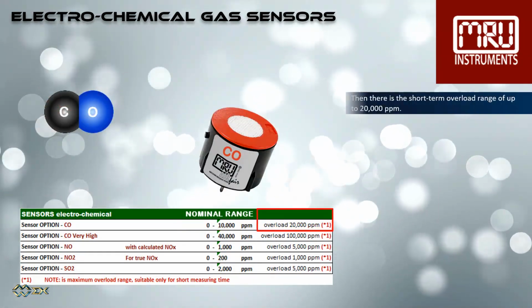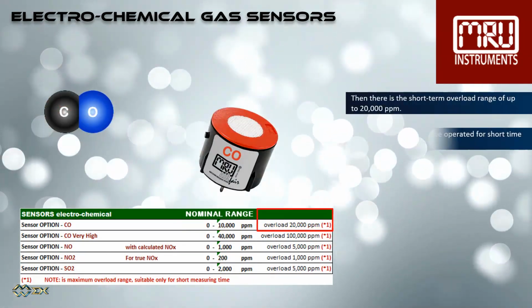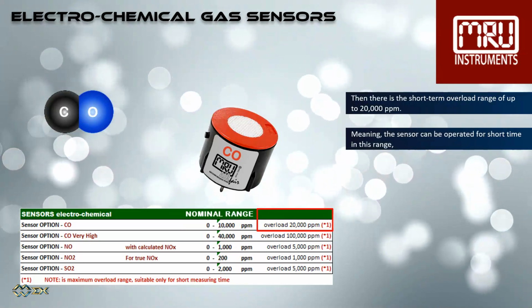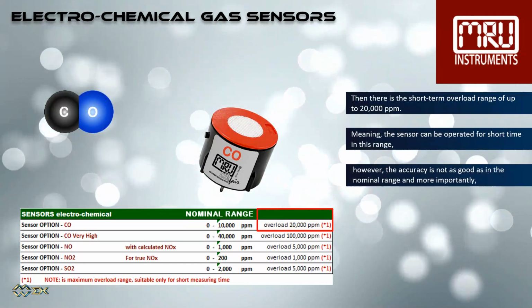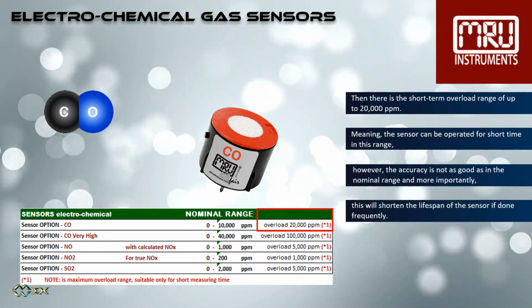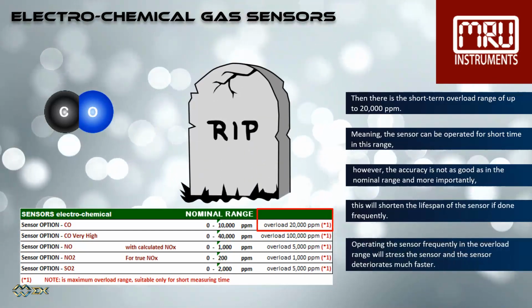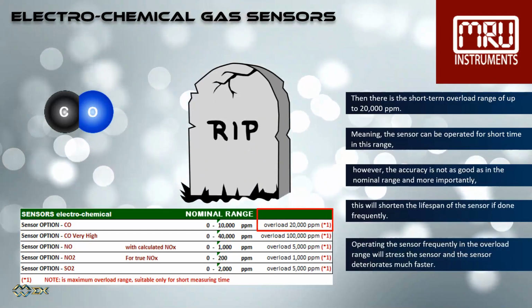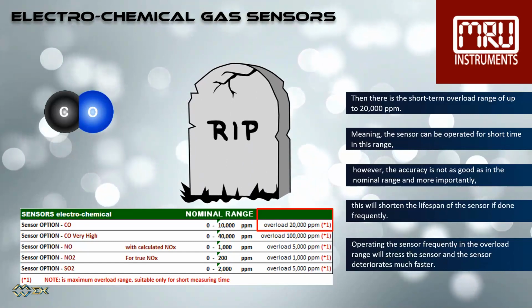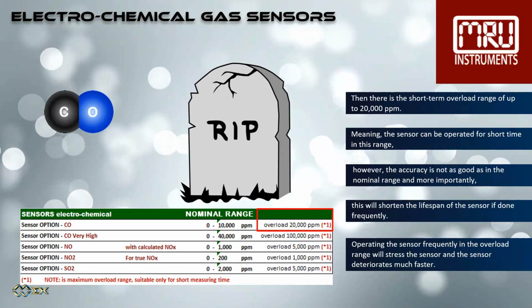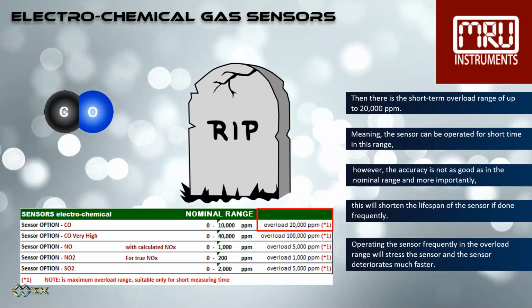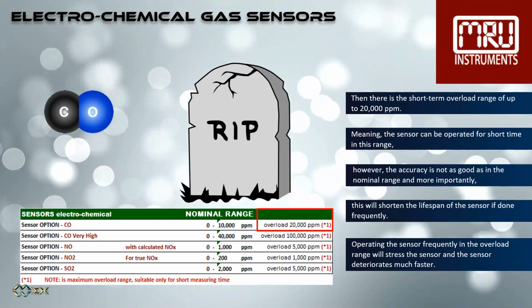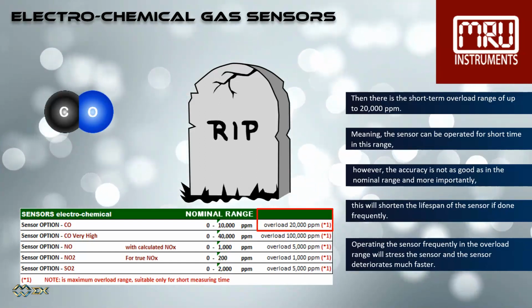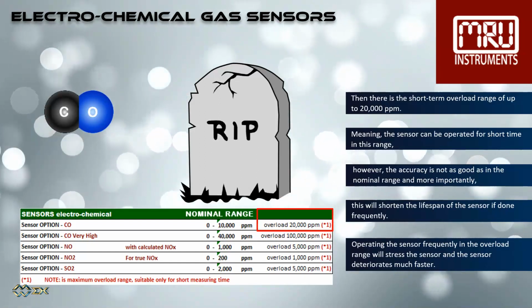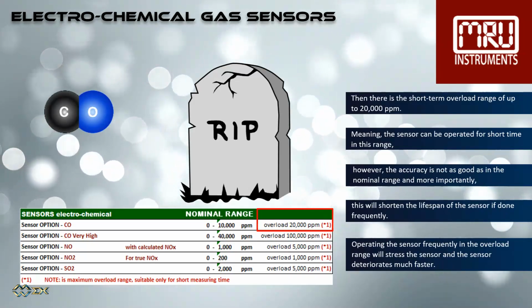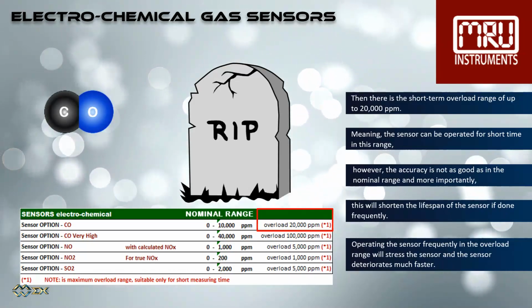Then there is the short-term overload range of up to 20,000 ppm. Meaning, the sensor can be operated for short time in this range. However, the accuracy is not as good as in the nominal range, and more importantly, this will shorten the lifespan of the sensor if done frequently. Operating the sensor frequently in the overload range will stress the sensor and the sensor deteriorates much faster. Operating the sensor above the overload allowance will destroy the sensor.